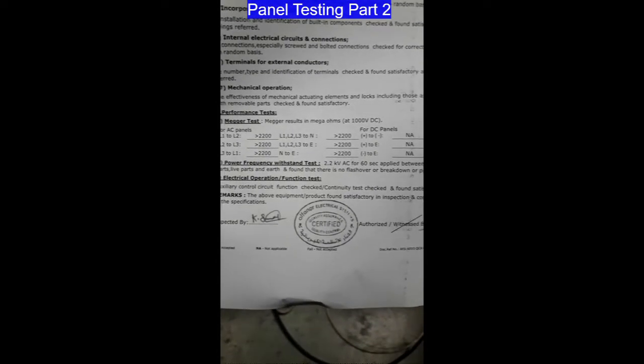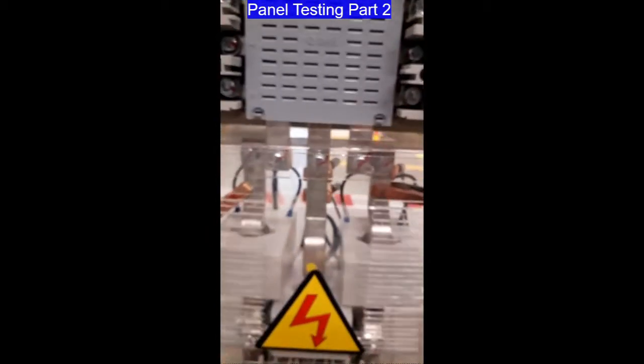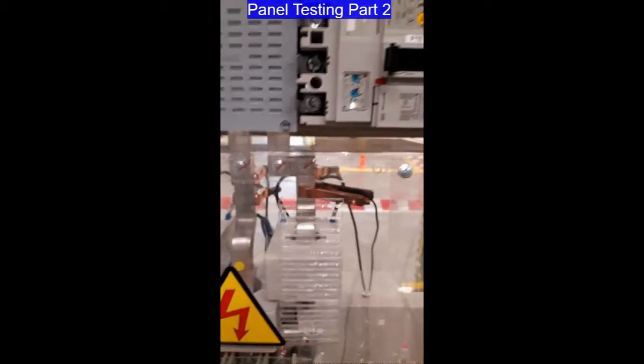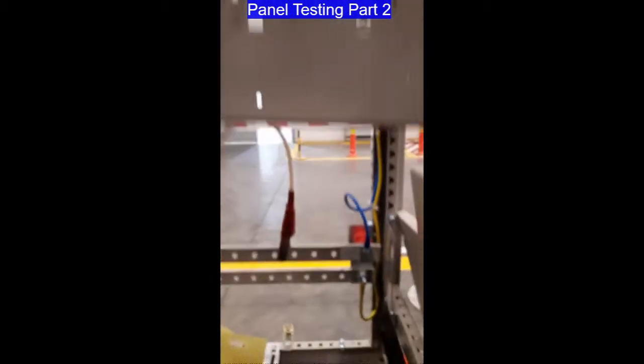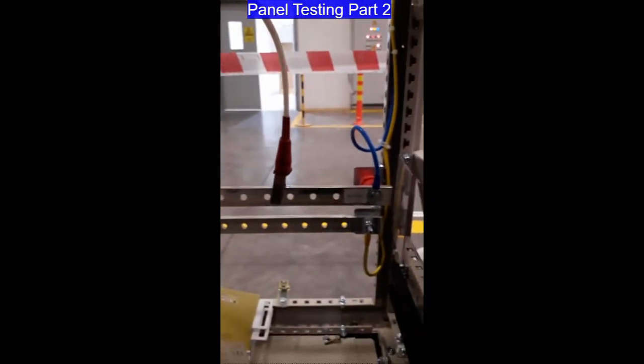High voltage power frequency withstand test, 2.2 kV for 60 seconds, applied between live parts and earth, and we found that no flashover, breakdown or puncture occurred. Here the connection is ready: line 1, line 2, line 3 are shorted and connected to the neutral. Now we are going to do it with the timer.